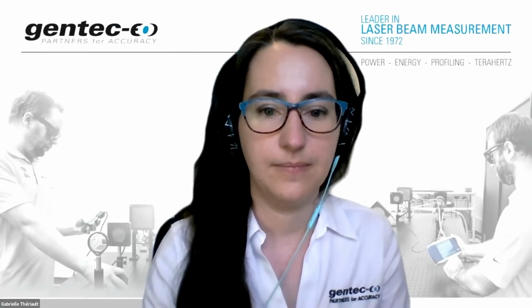Not sure I understand, but what I get from this question is to make sure, when you're doing the zeroing part, whether doing the zero too close right after you've blocked your laser is going to affect the zeroing. Okay, I see. Yes, it's good in any case to let the detector stabilize. If it's a photodiode, low power, that's really quick. The rise time is around 200 milliseconds, I guess. But for the thermopiles, it's usually 10 seconds.